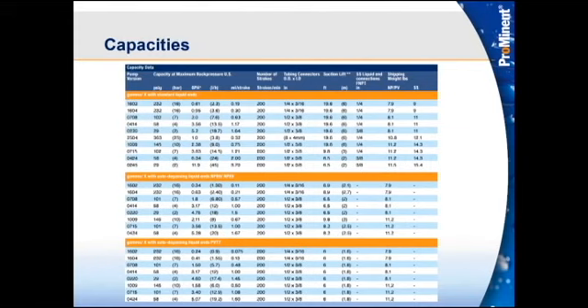Here is a look at the capacities the Gamma X is capable of. And notice, like I mentioned earlier, we now have three different charts. We have your standard liquid ends. Below that, we have the auto degassing, that's the 3 valve, that's that 9 option, the NPE 9 you may be familiar with. And then even further down, we now have that PVT 7 head. So keep in mind, if you're selecting one of those heads, it does derate the capacity of the pump.